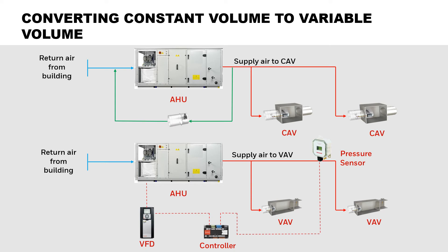The lower image is of a variable volume system. Here, the VFD controls the supply fan or system pump in conjunction with the dampers or valves. As the dampers and valves close, the system's pressure builds and the VFD slows down the fan or pump to maintain the system's design pressure. As the control dampers and valves open, the system's pressure declines and the VFDs speed up the fan or pump to maintain the system's design pressure. This allows all terminal devices such as diffusers, unit ventilators, etc. to receive the correct flow of air or water.